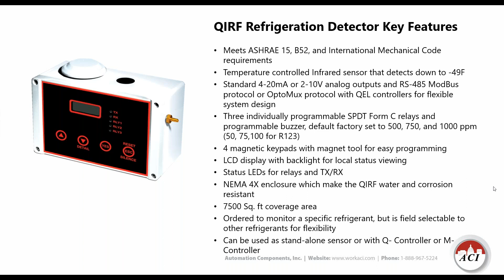Typically you mount this about 18 inches off the floor between, say, 2 chillers. A lot of people just mount it on the chiller's pad. If you've got 2 chillers with the same Freon, especially within that 7,500 square foot range, you don't need 2 Freon detectors. One will detect the whole area, usually mounted somewhere between the 2 chillers.